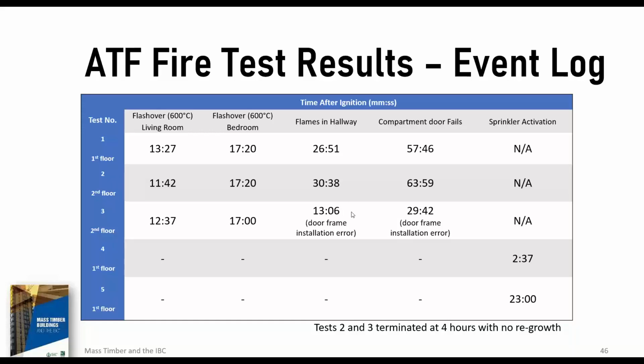We had a little hiccup on test number 3 where the door frame installation went awry. So we didn't get as much fire resistance out of that 20-minute rated door as we would have liked. As you saw in the video for test number 2, the compartment door held out for almost 64 minutes, very close to an hour for test number 1, and again, an accelerated failure rate at just about 30 minutes for test number 3. We didn't have any compartment door failure issues with tests 4 and 5 because they didn't go along that far.